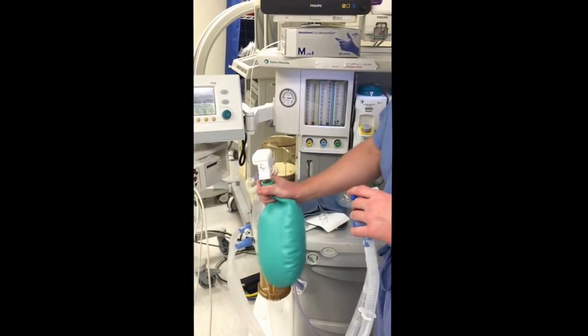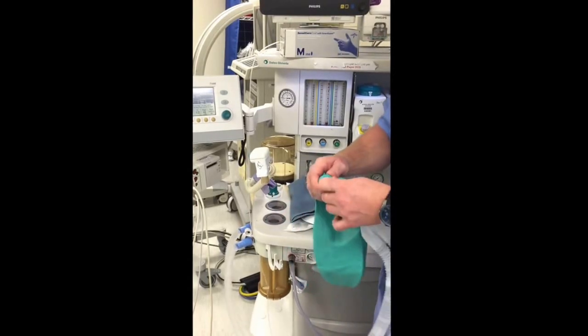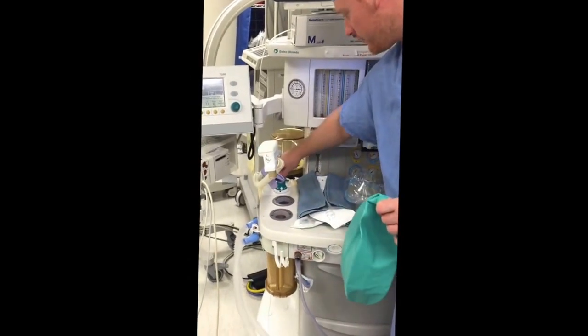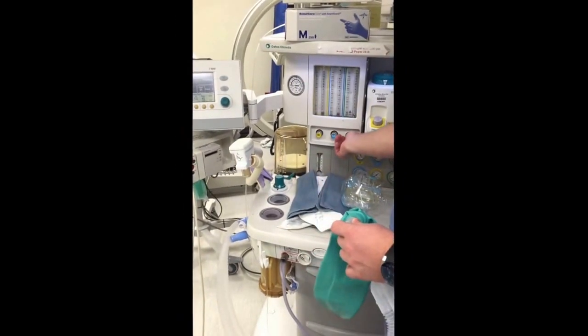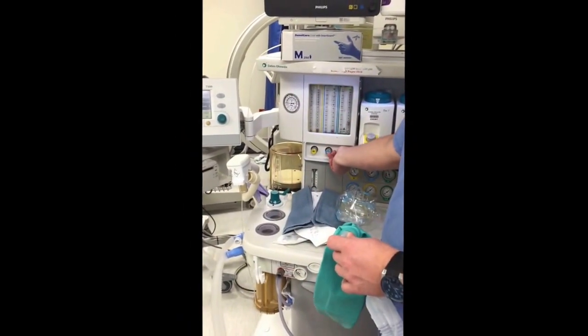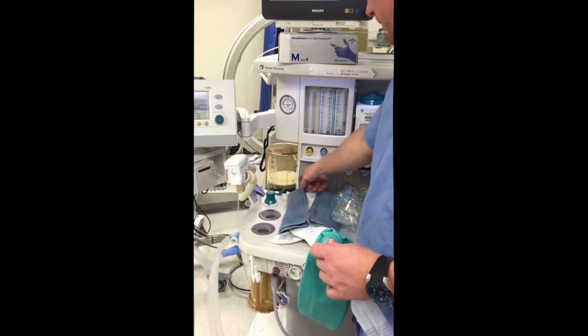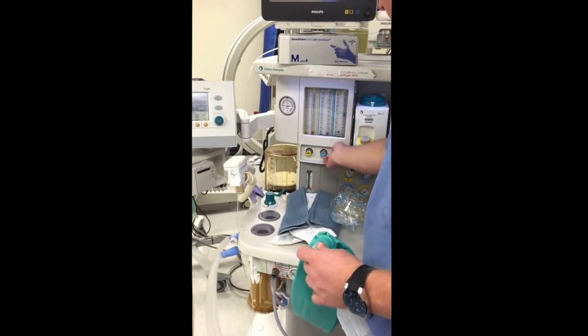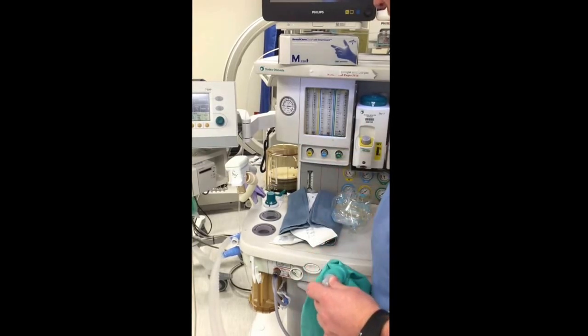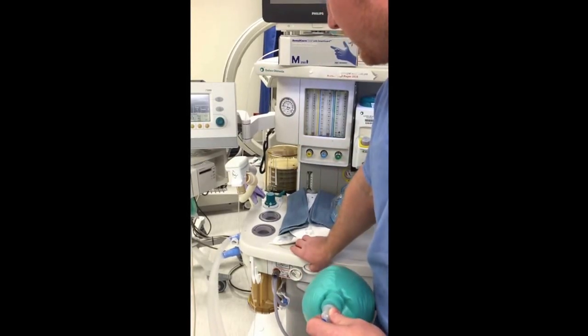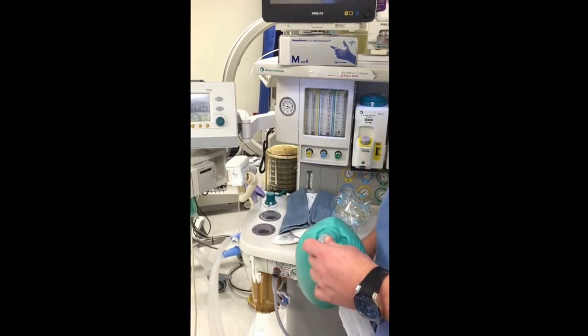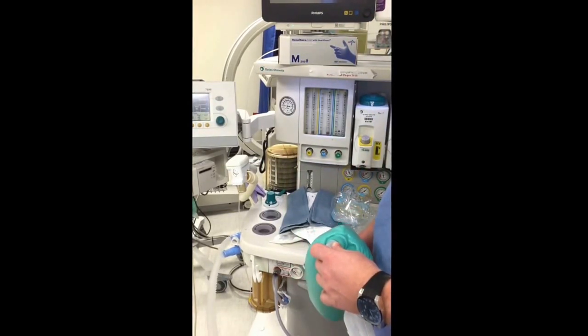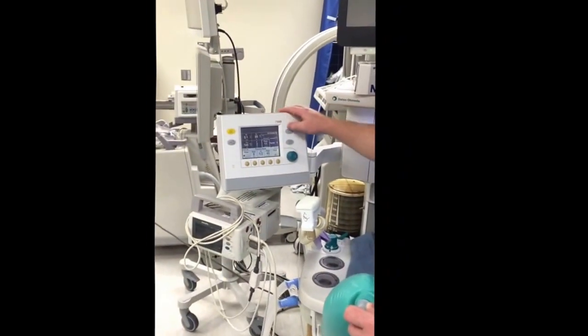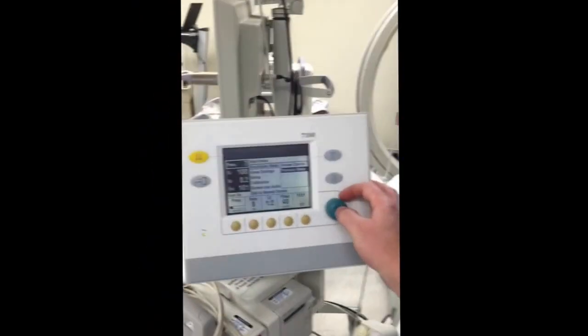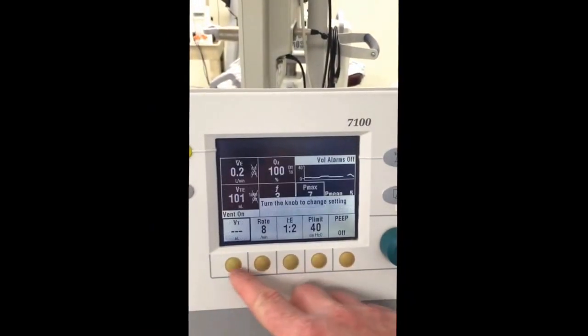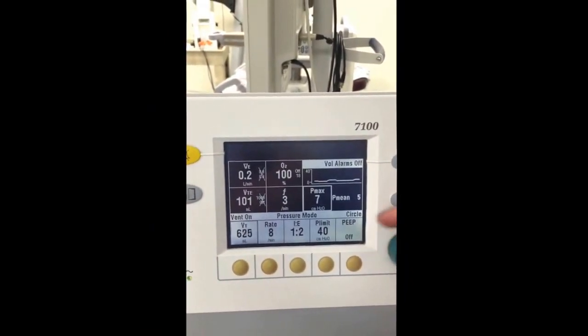Next, you would check your ventilator by removing the bag, placing it over your Y piece, and switching to the ventilator mode. As you can see, the bellows don't fill, so you have to get either enough fresh gas flow, or you can hit your O2 flush valve as long as it's not during inspiration. And then at this point, I like to set my ventilator mode for my first patient of the day so that it's all set.